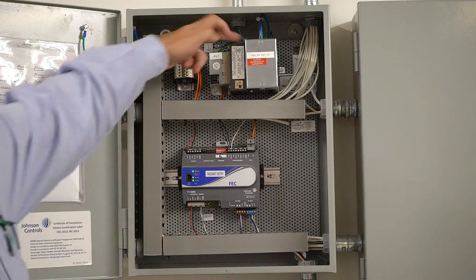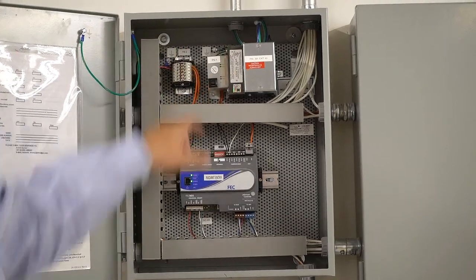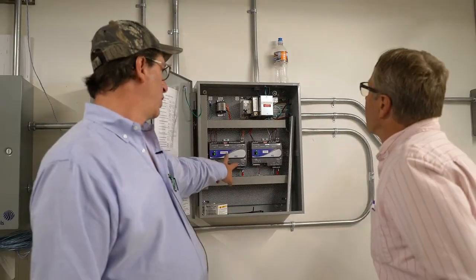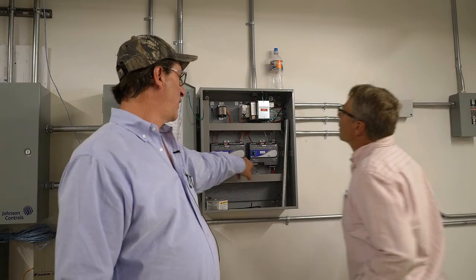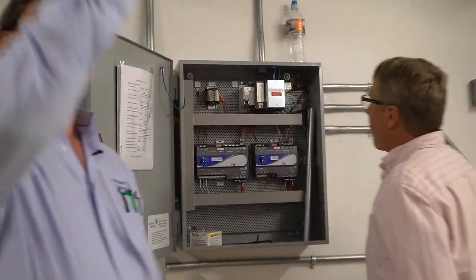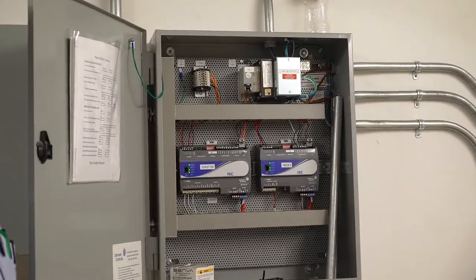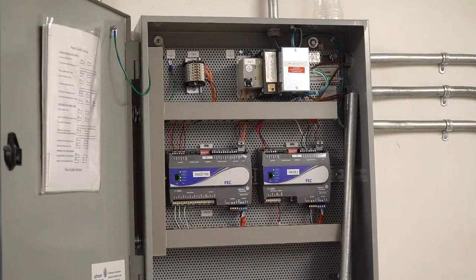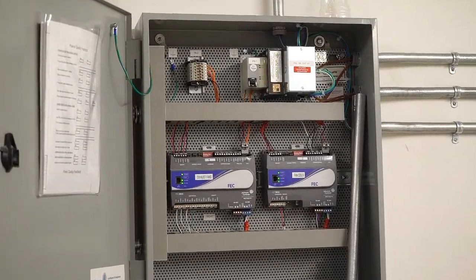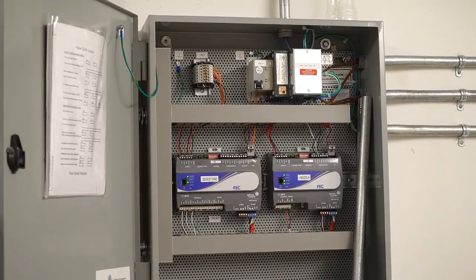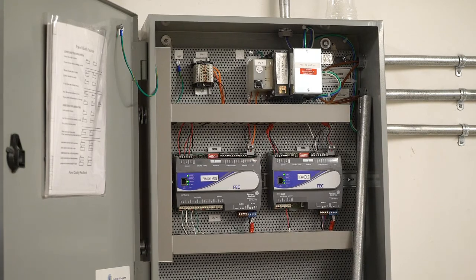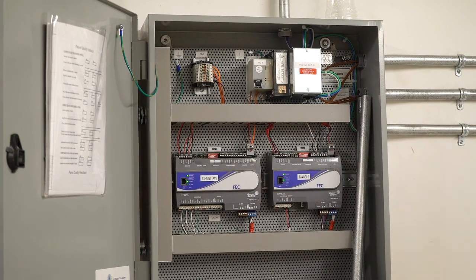Again, panel, same thing. You have your shutoffs up here, your resets right here. So this FEC controller is for the exhaust fans. This FEC is for fan coil 9, which is above our heads. You can also see up here the heating valves, the blue one. You can see the indicator up there for the position of the valve. There's also a relay on top of that box, and that would be our standard RIB relay with the red light to tell you when it's enabled. That's going to be typical of anything that we're commanding.